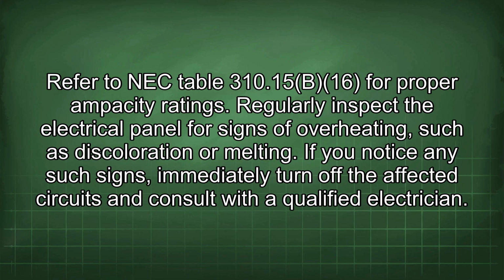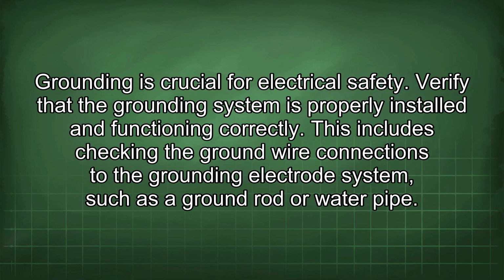Regularly inspect the electrical panel for signs of overheating, such as discoloration or melting. If you notice any such signs, immediately turn off the affected circuits and consult with a qualified electrician. Grounding is crucial for electrical safety. Verify that the grounding system is properly installed and functioning correctly. This includes checking the ground wire connections to the grounding electrode system, such as a ground rod or water pipe.